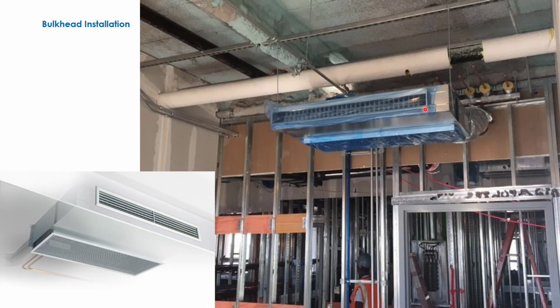Now, this is what you might call a bulkhead or a horizontal chill beam. This is actually what it will look like when it's all furred in with the drywall. The return air comes in through the bottom. It jets out through the front grill, which you can see right here. You can see the bottom return. And up here, if you have a look, you can see the contractor has roughed in the water connections. They're capped off so they can do the pressure testing, and after all the testing's been signed off, they can cut these things off and do the final connections. You're going to want to isolate the chill beams for the flushing process, and do the connections in here. And of course, as the drywall goes in, this will get harder and harder to work around.